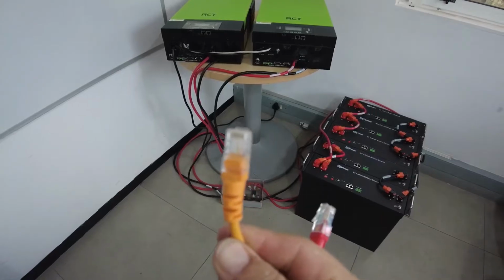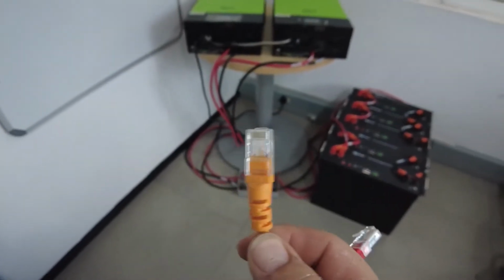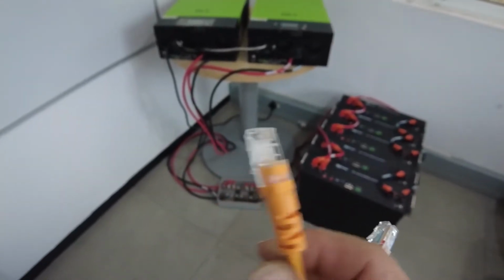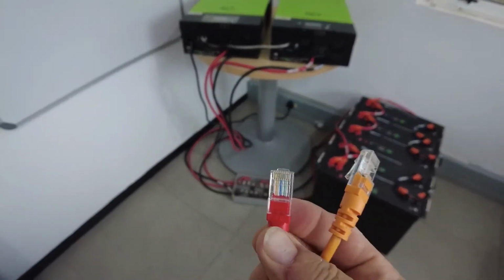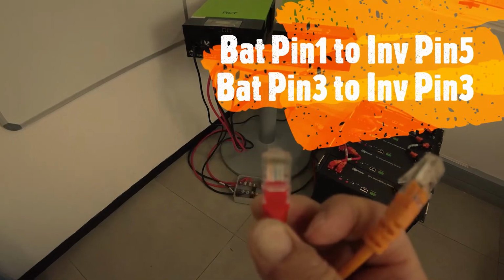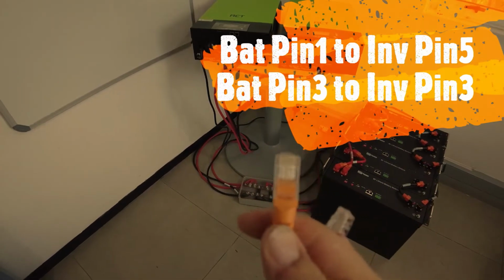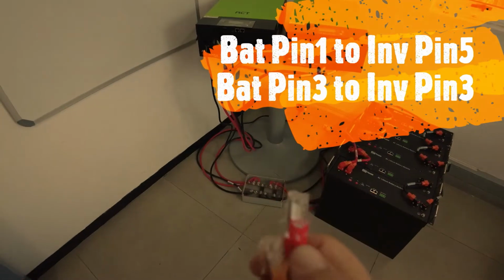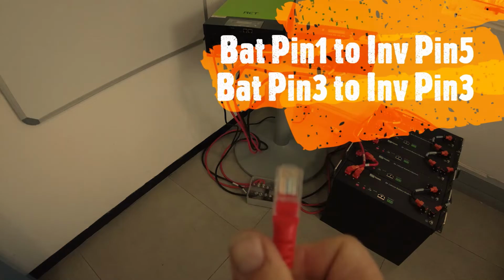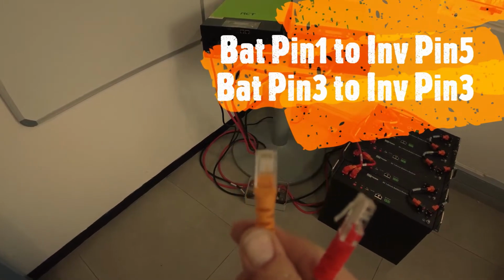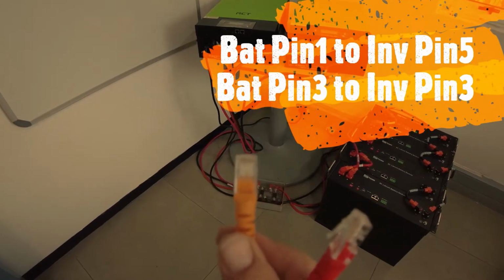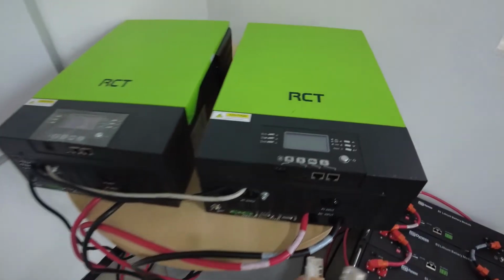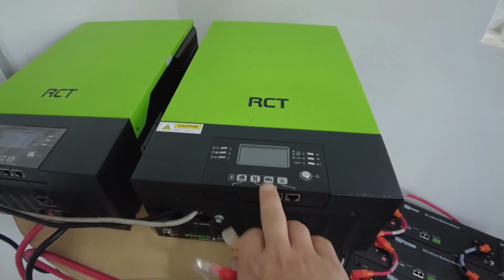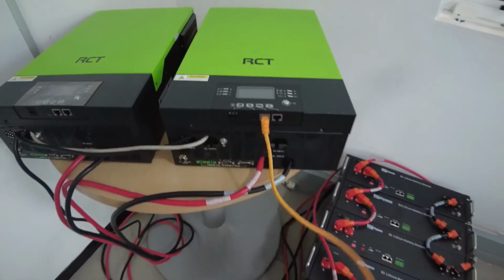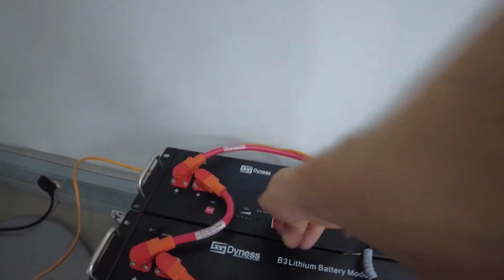So you will need to snip the RJ45 on the inverter side so you can rewire the RJ45 plug. On the battery side, pin number 1 is your orange and white. Will go to the inverter side, pin number 5. And then battery side, pin number 3, green and white, will go to your inverter side, pin number 3. Inverter side, you will connect to your inverter marked with lithium ion, and then your battery cable will be connected to the first battery.